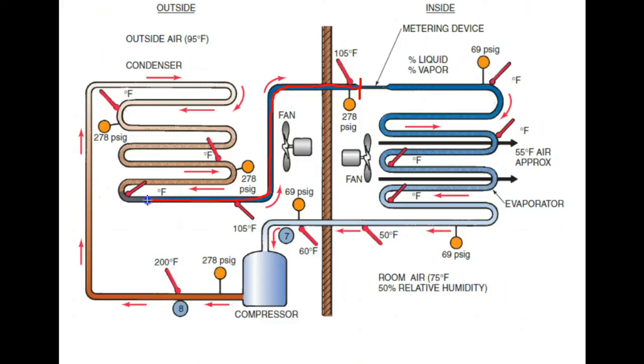This column of liquid begins at a certain point near the end of the condensing coil. That allows the system to shed more heat from the liquid refrigerant and give us about 10 degrees of sub-cooling. Now the sub-cooling levels will be different for different equipment and manufacturers, but in this example we're going to use 10 degrees. So this is operating properly, charged properly, solid column of refrigerant, and it becomes liquid at this point in the system and it's backed up right here as it should be.